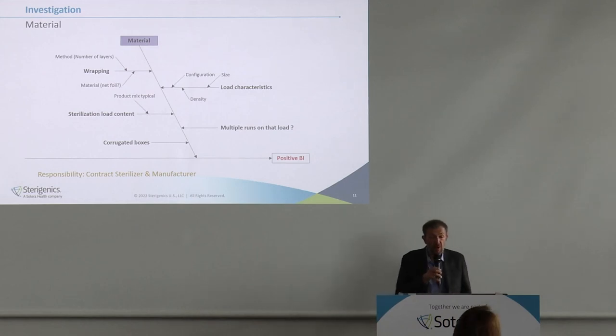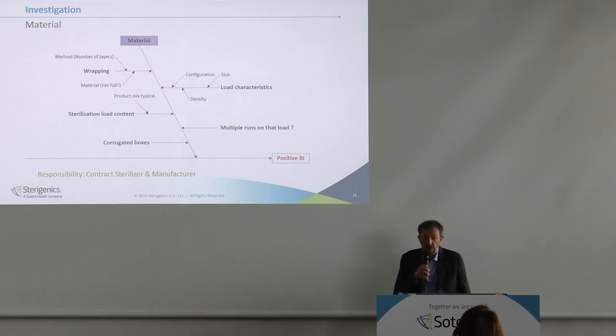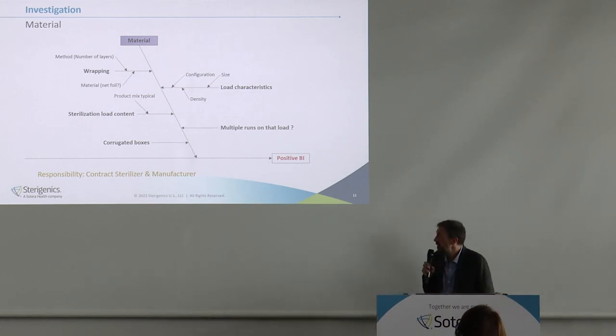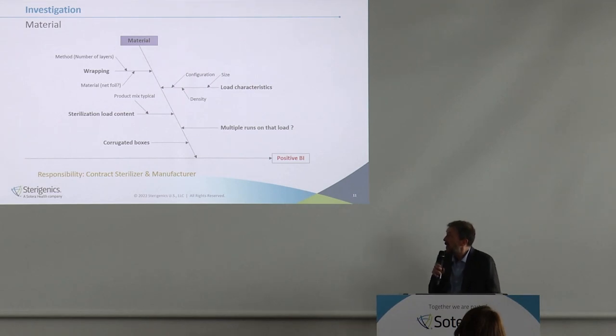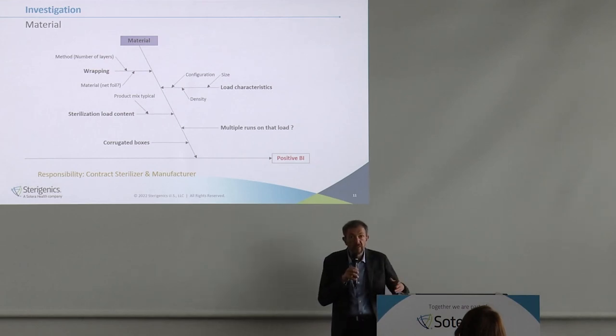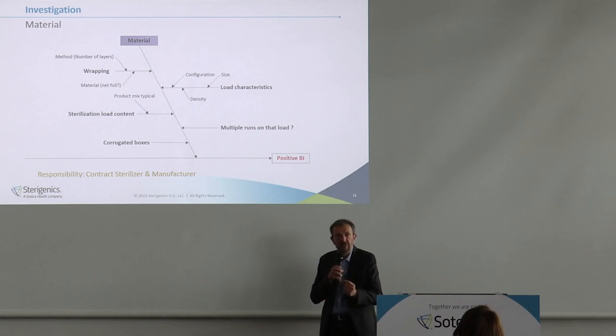The fourth pillar to check is the material itself. Products are sent to sterilization in boxes, and to stabilize them on pallets stretch wrap is used — we need to check if the same stretch wrap and the same number of layers were used as validated. For me the most important element here is the load configuration: if it's different from what was validated we may have an explanation. The size of the load — larger or smaller than validated — may impact gas absorption, and density is a key factor because a denser load takes longer to heat.